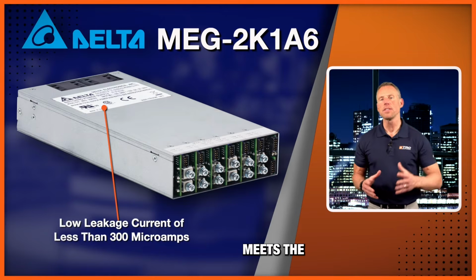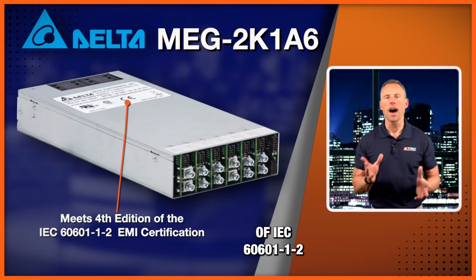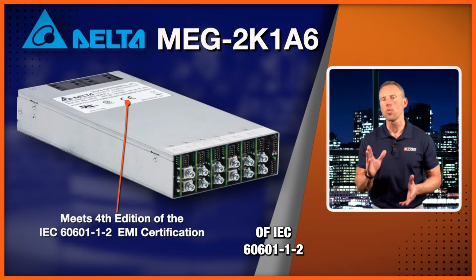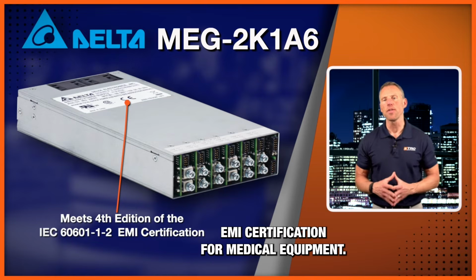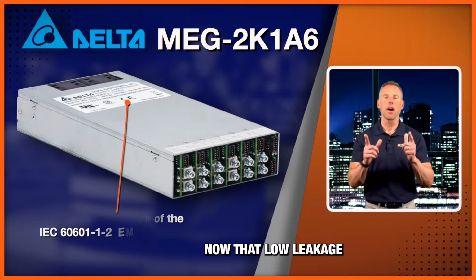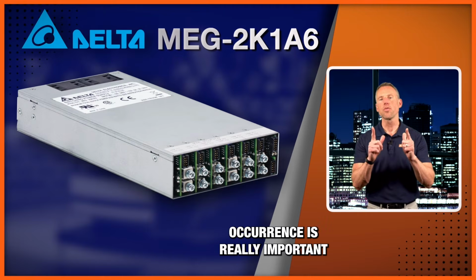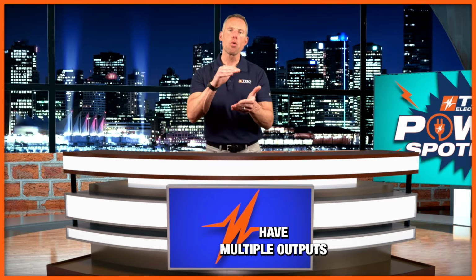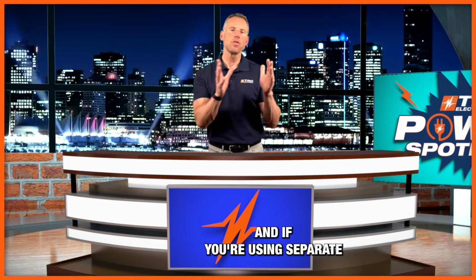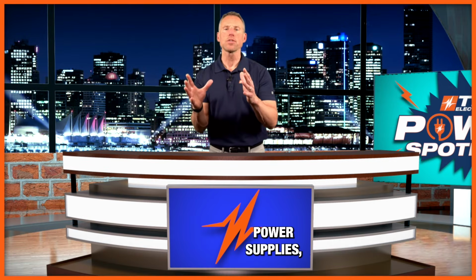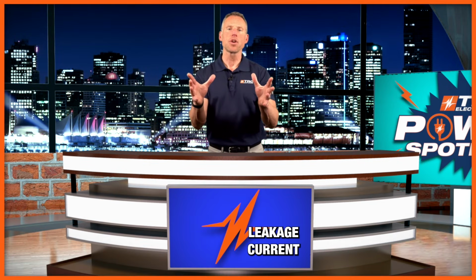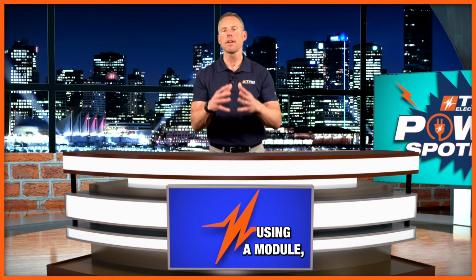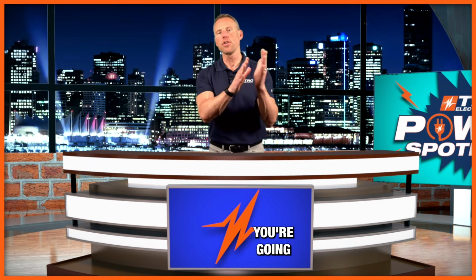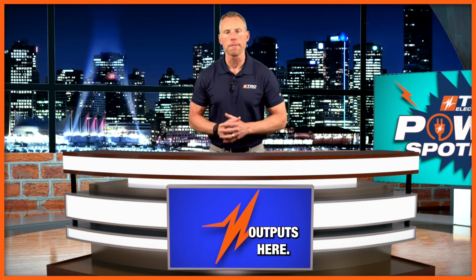This unit also meets the latest 4th edition of IEC 60601-1-2 EMI certification for medical equipment. That low leakage current is really important, because if you have multiple outputs using separate power supplies, you won't meet the leakage current spec. But when you're using a modular supply, you get that low leakage current by combining all those different outputs.